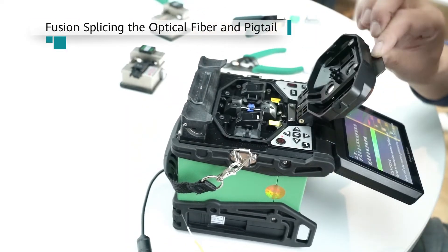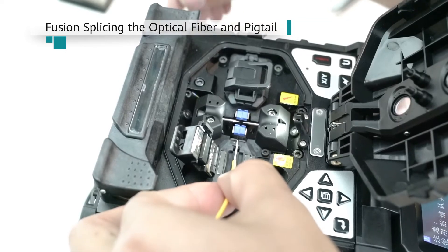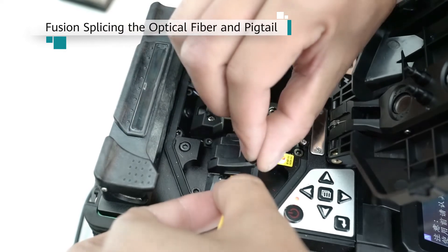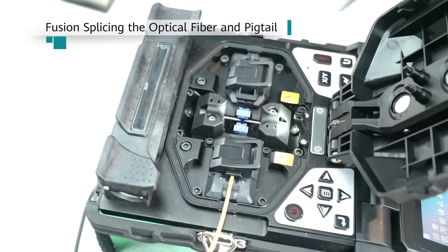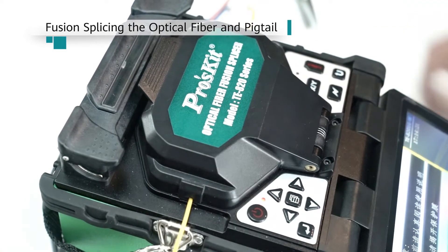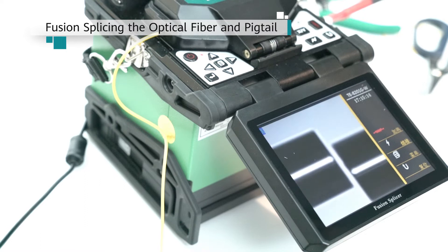Place the optical fiber and pigtail into a single core fiber fusion splicer. Use a 0.9 mm trough for the pigtail and a 0.25 mm trough for the optical fiber. Power on the fiber fusion splicer to fusion splice the optical fiber and pigtail.